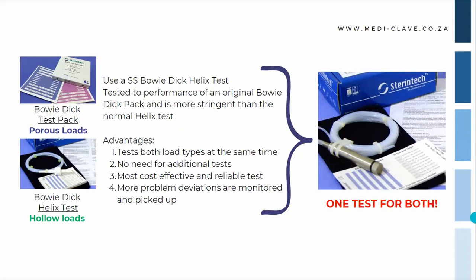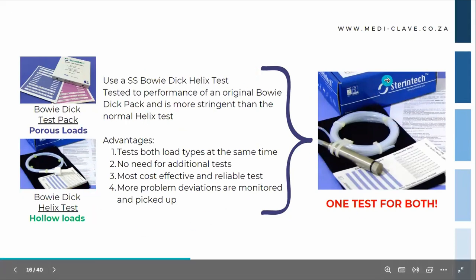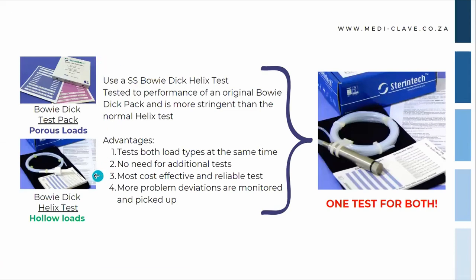So the stainless steel Bowie Dick helix test will replace both the Bowie Dick test pack as well as your Bowie Dick helix test. It tests for porous loads and hollow loads. So it's one test that you'll use instead of having to use both of these tests. Advantages are it tests both load types, as I've just mentioned. There's no need for additional tests. It's most cost effective and reliable, and shows more process deviations.